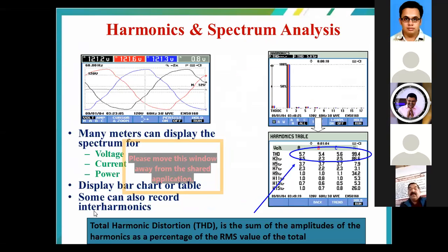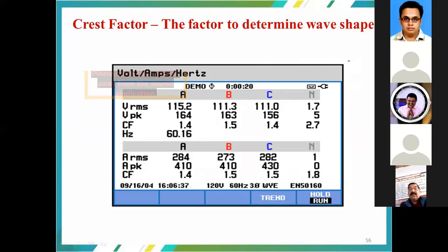And the harmonics and the spectrum analysis are as shown. In the case of harmonics, the waveforms are going to get distorted. In the case of the other ill effects, the voltage, current, and power are going to be distorted, and the power is going to get increased. The current waveform is going to get distorted. While going for the measurement, we are going to have a bar chart, which represents the level of the THD as well as the fundamental component. And this is the wave. This is the Fluke power harmonic analysis screenshot, which gives the crest factor, the factor which determines the wave shape.